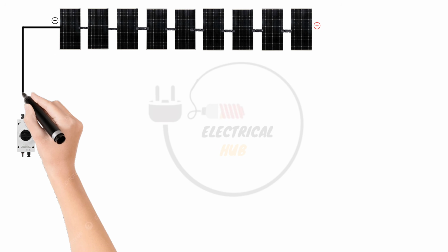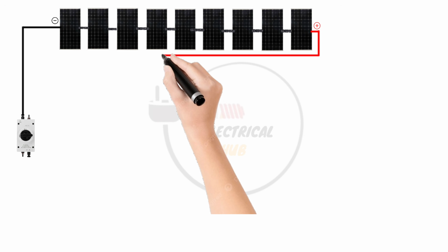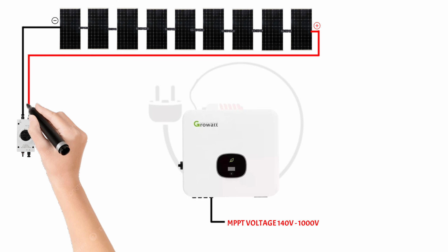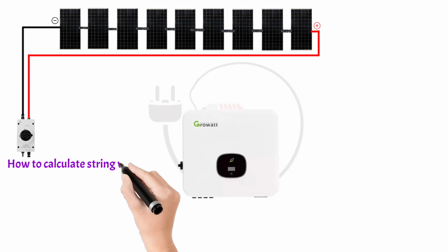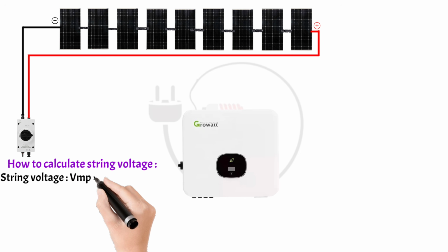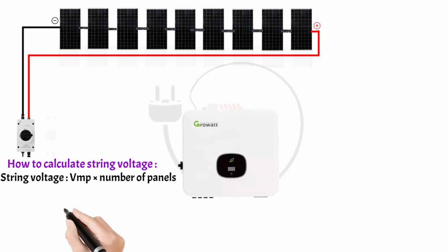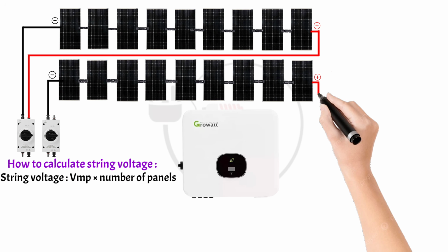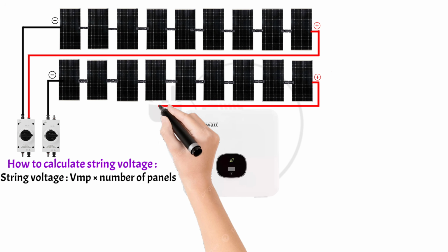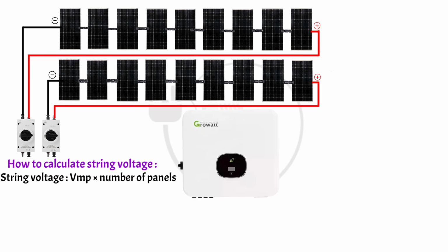Crucial step: voltage check. String voltage. You must ensure the voltage of your solar string falls within the inverter MPPT voltage range, 140 volt to 1000 volt. How to calculate string voltage? String voltage: multiply the panel's VMP by the number of panels in a string. String configuration. You need to decide how many panels you have in each string and how many strings you will have. This depends on the panel voltage and the inverter's MPPT trackers. Example, you could have 2 strings of 9 panels each, total 18 panels, or another configuration. Ensure the voltage of your solar panel strings is compatible with the inverter.